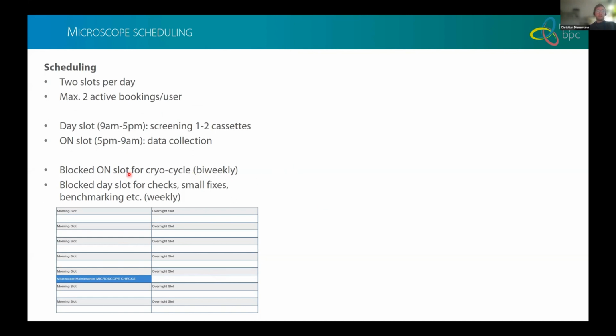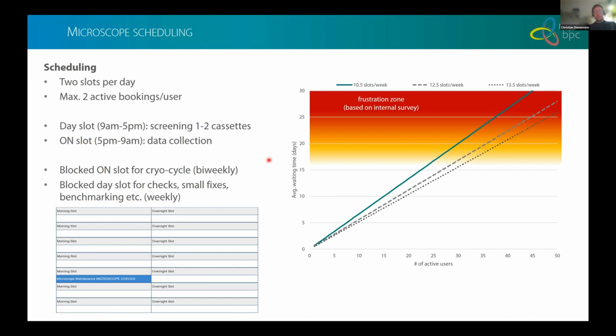We bi-weekly block an overnight slot for cryocycle, and we block a day slot every week for small fixes, benchmarking, checks, whatsoever. And this actually helps a lot to keep the microscope running, because when there is a small thing to be changed, checked, or fixed, then we can use this pre-blocked slot for this. And recently we started using this for collaborations. With this kind of scheduling, our theoretical waiting time, which is along the green line, with 20 to 25 active users, is right around 15 days.